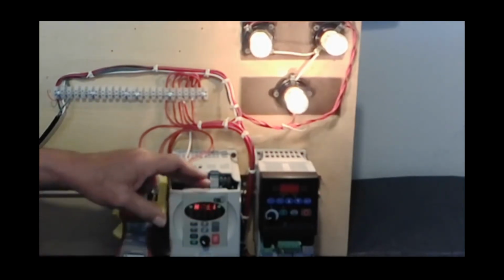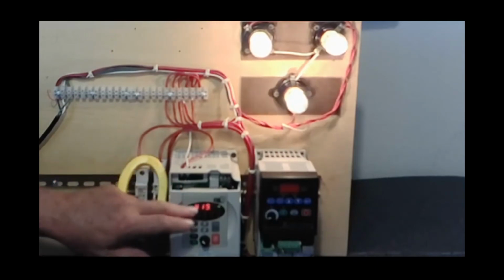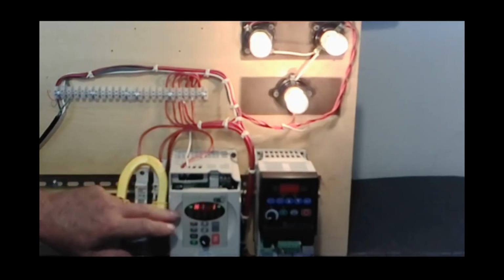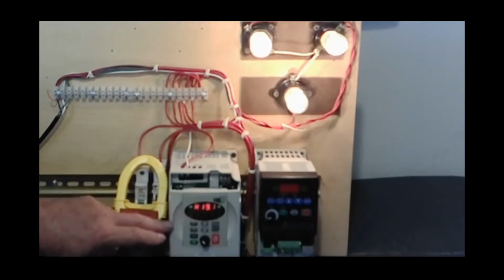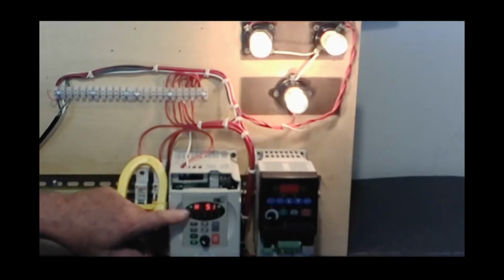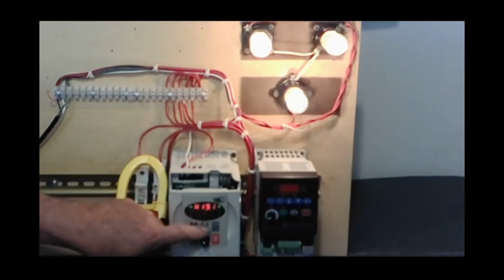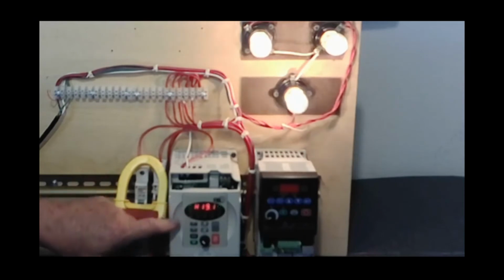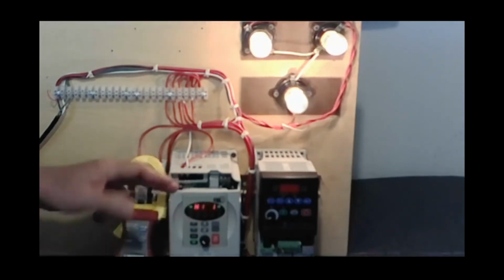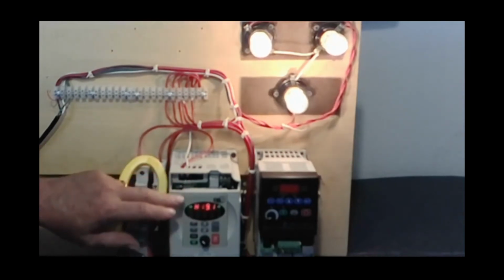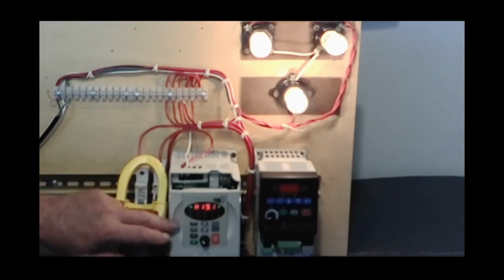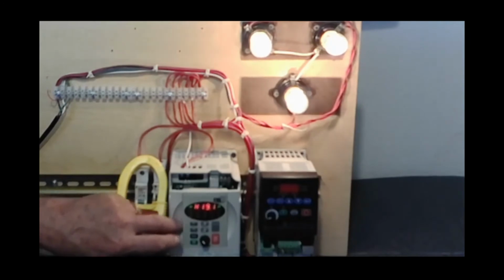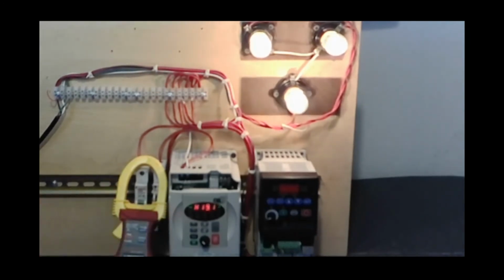If the drive will not start or run correctly, it could be in the programming itself. Programming itself, which again shows you error codes, but there's also programming codes throughout this drive. And these programming codes, I can go through those, and how that works is, again, I have to have the drive manual. And every one of these codes will have a different function. So that's a whole other story based on specific types of drives.